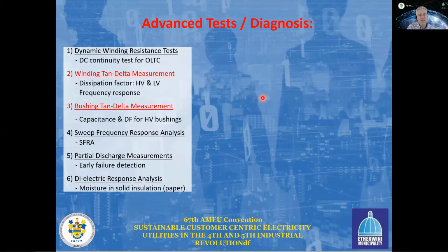The second test that should be done is the tan delta measurement on both the winding as well as the HV bushings of a power transformer. This is also commonly referred to as the dissipation factor measurement between your high voltage winding and your low voltage winding. And we do this not only at a single frequency, but in a range of frequency from typically 15 Hertz up to 400 Hertz.